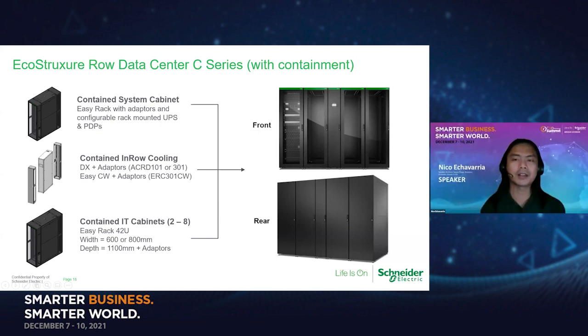This is standalone—you can put it just inside your IT office. It can expand from 2 racks to 8 racks depending on the requirement, and can be either split type unit or chilled water, depending on the cooling availability in your room. As you can see, this is a wholly contained solution—we call it the EcoStruxure Row Data Center. Everything is contained, so you don't need to build a room.